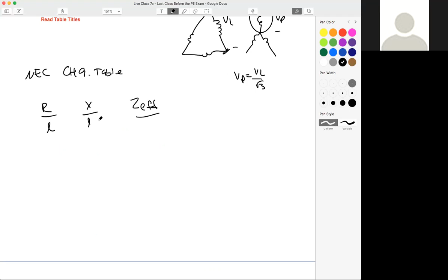It says if you have a power factor of 0.85, you take your Z effective value. So if you know your L, your Z effective is ohms per L. You multiply it by your L, and you have your total resistance in ohms. So in essence, you treat your Z effective as a magnitude per your 1,000 feet or whatever unit of length you're working in. Treat it as a magnitude per your length.